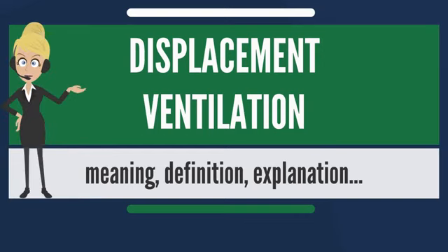Displacement ventilation is a room air distribution strategy where conditioned outdoor air is supplied at a low velocity from air supply diffusers located near floor level and extracted above the occupied zone, usually at ceiling height. A typical displacement ventilation system, such as one in an office space, supplies conditioned cold air from an air handling unit (AHU) through a low induction air diffuser.